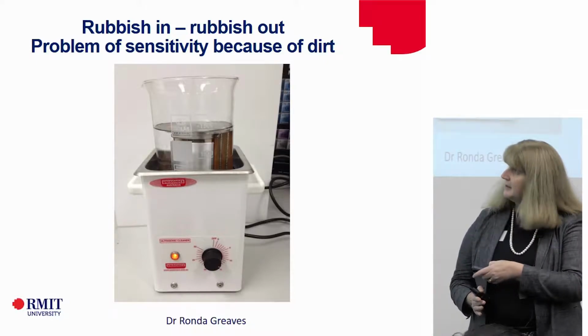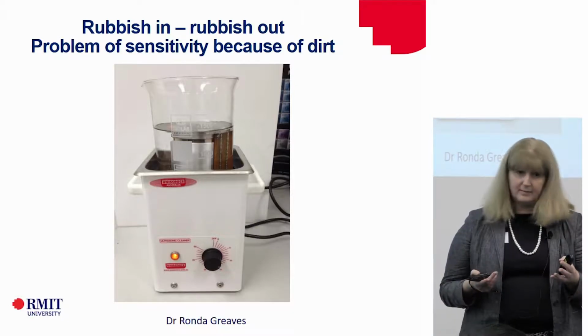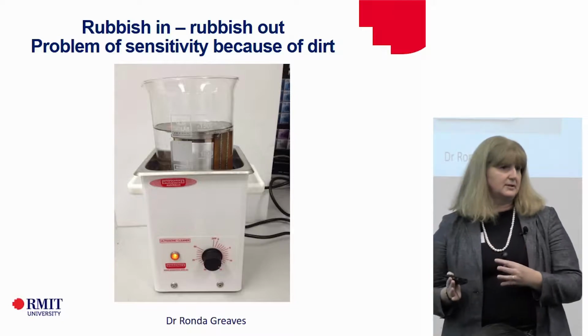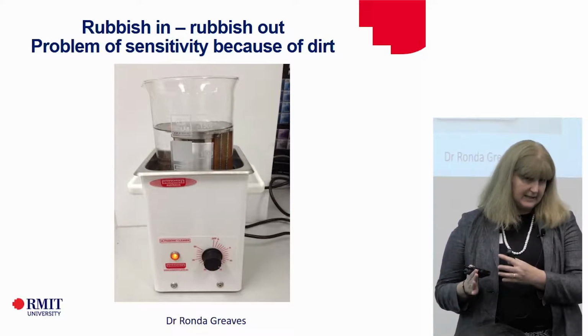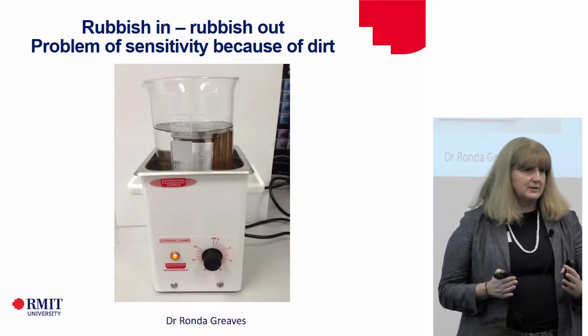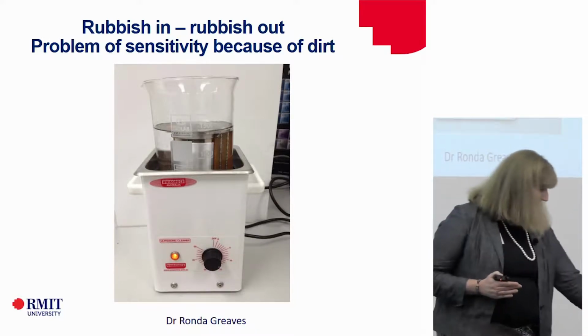And this is part of the mass spectrometer just having a bit of a clean up, because if it's dirty, or we've put dirty samples in it, and I've seen some really dirty samples go into other mass spectrometers, they're useless. And if we don't know enough about the mass spectrometer and we don't know how clean it is, we don't understand the quality of our results being generated. And so having key operators is, I think, really important, who you can trust to actually look after it, okay? And I think we have a lovely example in the room with Monday.